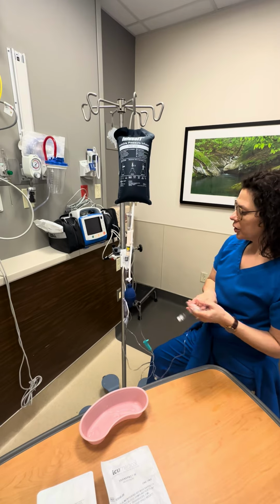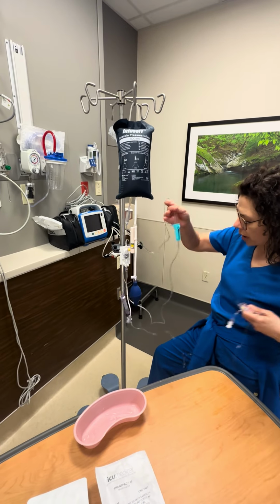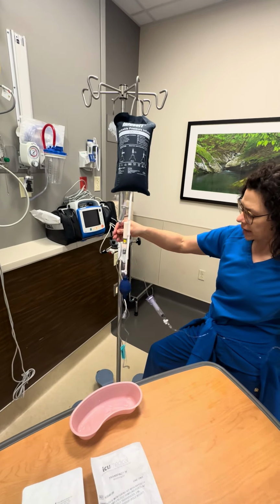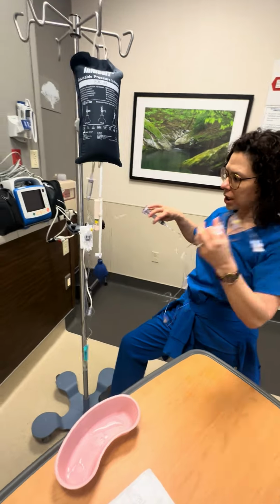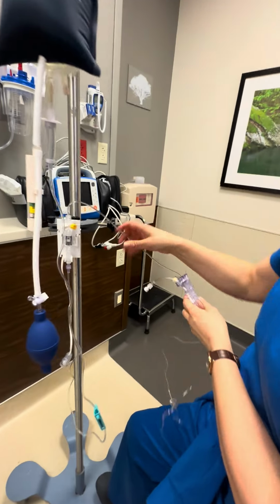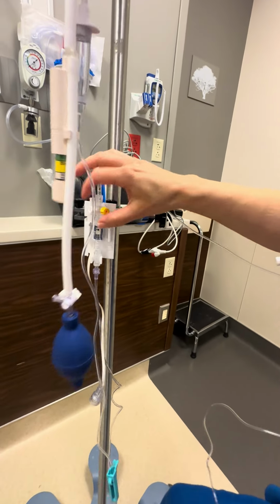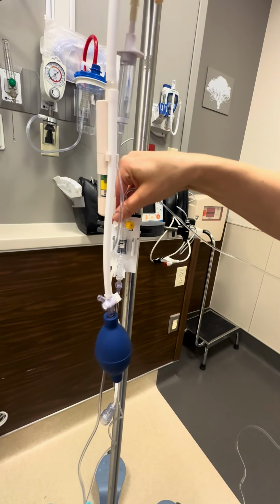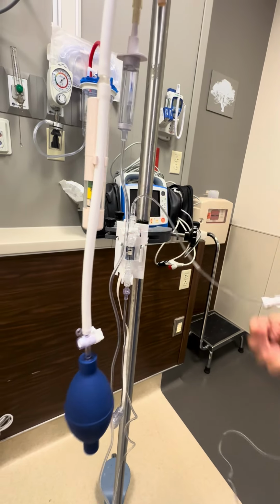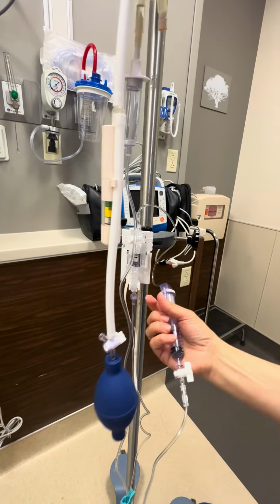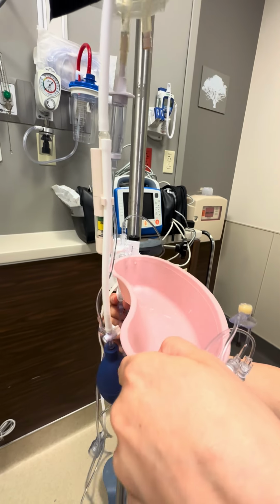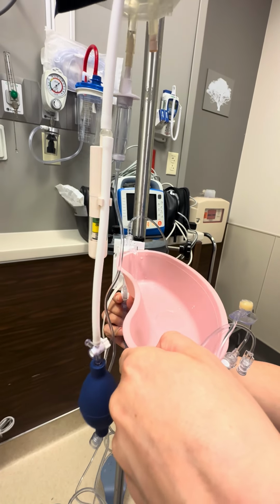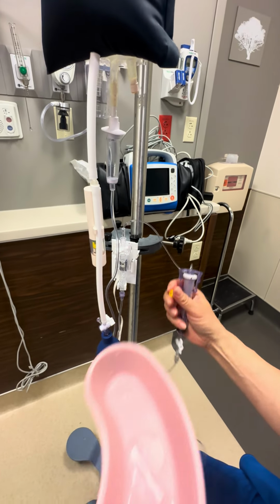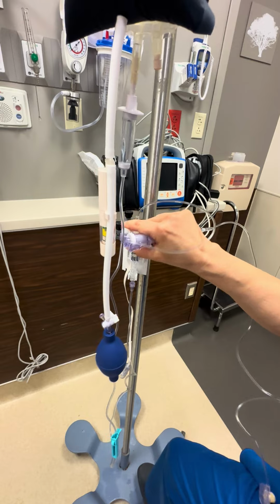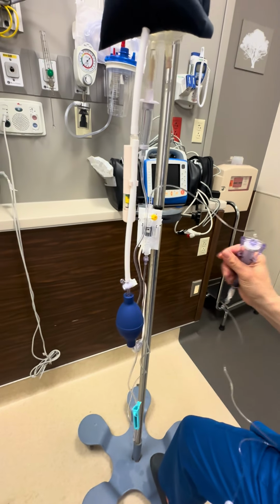The next thing that you're going to do is there's 2 areas to the priming. So you're going to be priming to the bag to atmosphere and then priming to the patient line. Patient line comes up off the top. So what you're going to do is you're going to actually open here, so let me get this off, to the atmosphere, we call it, and you'll see the water come through. So of course this line is primed already, but you'll do that until you have 0 bubbles. Replace that, and then you're going to turn it off to atmosphere.